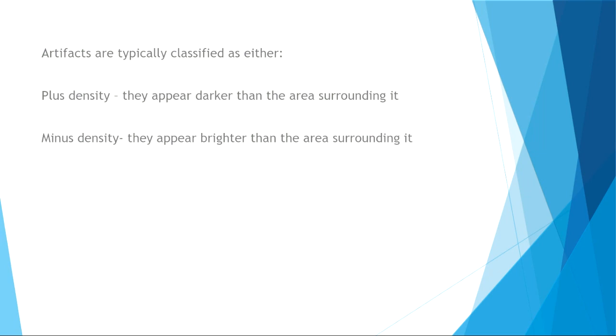It just depends. Usually you have to try and figure out how it was created. So looking at the imaging plates, occasionally cleaning those plates is important. And the imaging plate is inside the digital receptor, so those do have to come out sometimes and actually be cleaned. If a plate is damaged, noting that so that people don't reuse that plate until it's repaired is important.